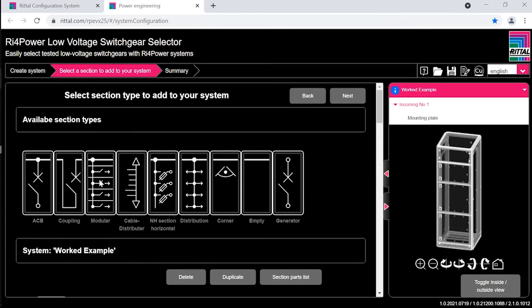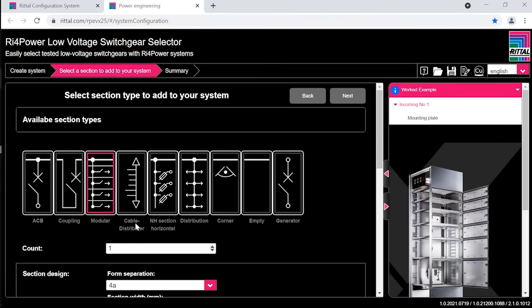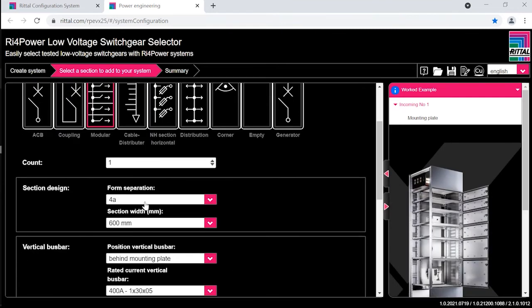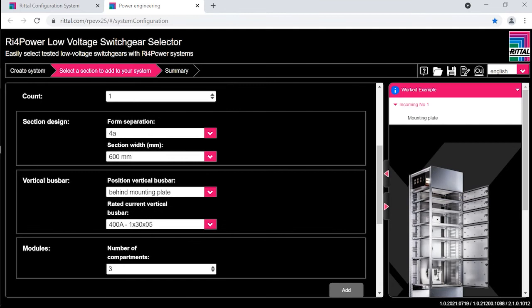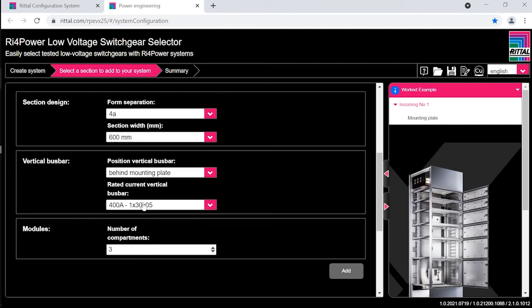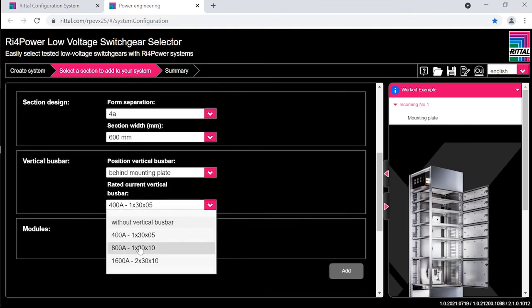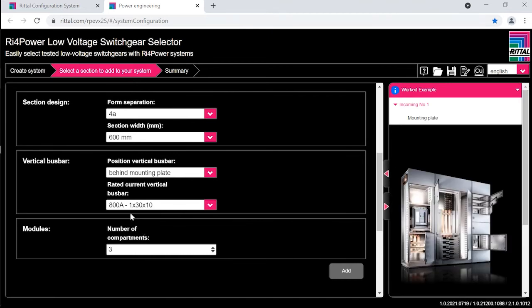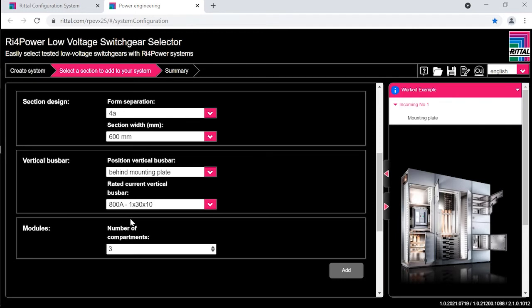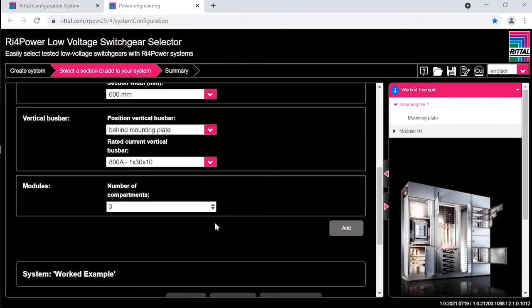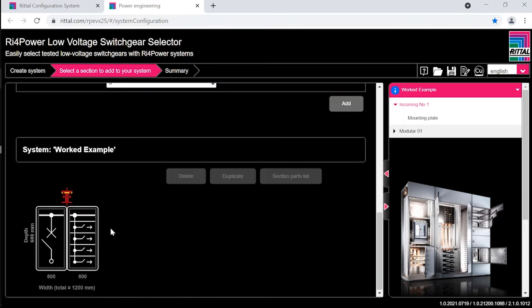Now we need the outgoing section. So click the modular section. It defaults to form 4A. It's 600 wide. The vertical bus bars are behind the mounting plates, and the rating we require is 800 amps. So we're splitting the load approximately 50-50. So I'll leave that a compartment with 3 doors just to show you how easy it is to change. So now we've added the outgoing section.